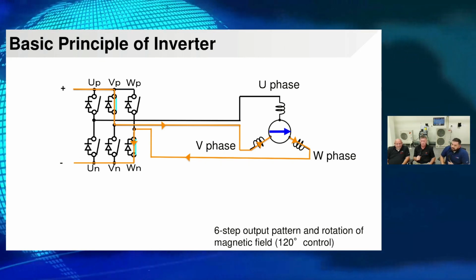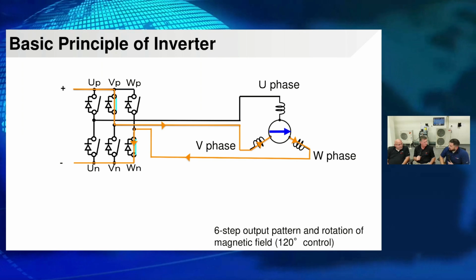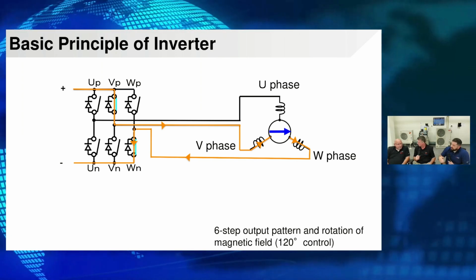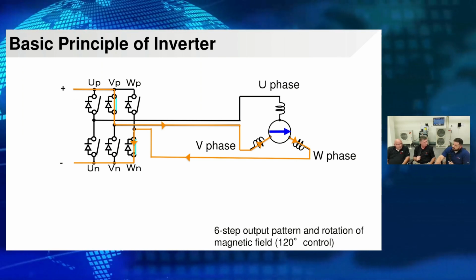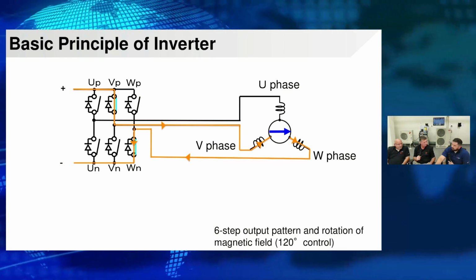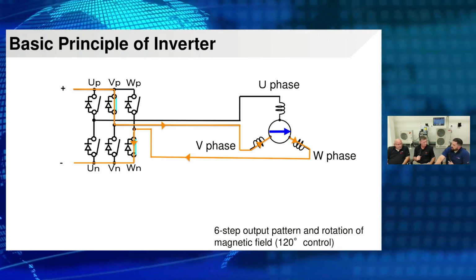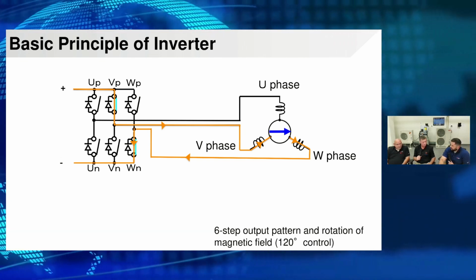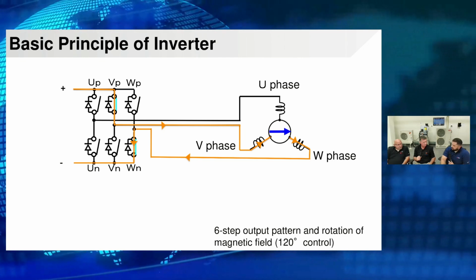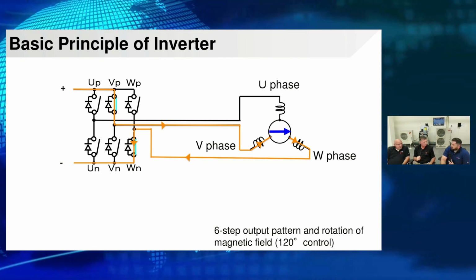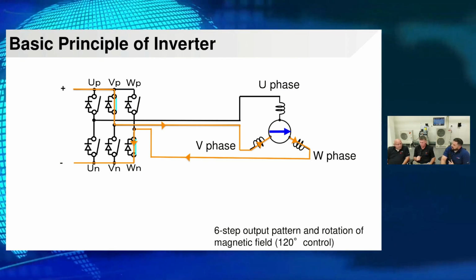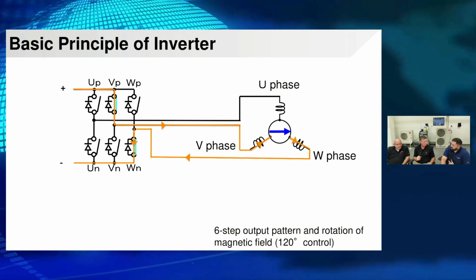We'd mentioned earlier, we're looking for balanced voltage. That's the most important part when we're testing the inverter side, right? When we're testing a compressor, that doesn't change with any compressor. We're going to ohm across windings, and we're going to check for shorts to ground, the same as we would with anything else. When we're testing our inverter, really we're just checking AC voltage on each leg of that compressor, making sure that we're plus or minus 10% on our residential.